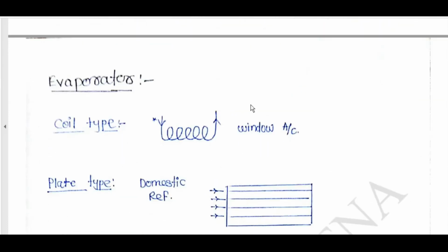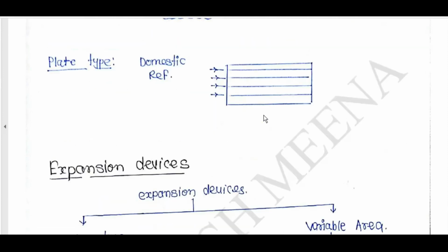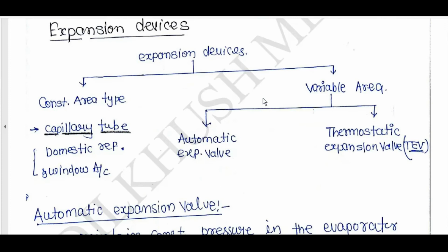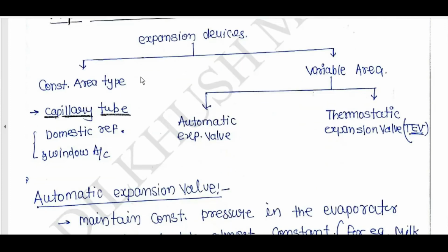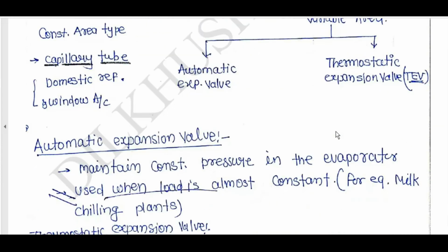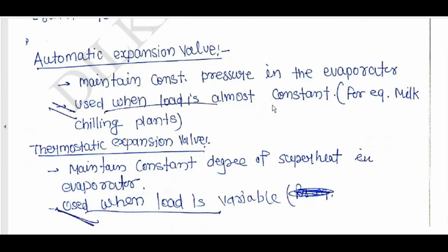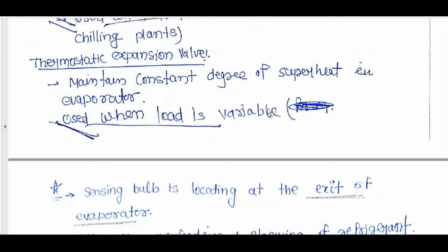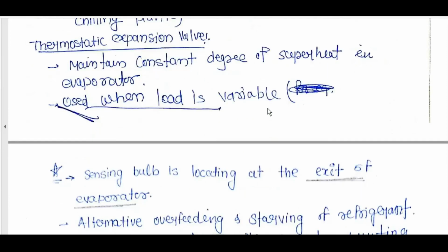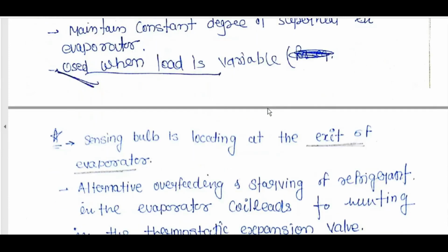Evaporator: coil type, window air conditioning; plate type, domestic refrigerator. Expansion devices: constant area type, capillary type, domestic refrigerator, window AC; variable area, automatic expansion valve, thermostatic expansion valve, TEV. Automatic expansion valve maintains constant pressure in the evaporator, used when load is almost constant, for example, a milk chilling plant. Thermostatic expansion valve maintains constant degree of superheat, used when load is variable.